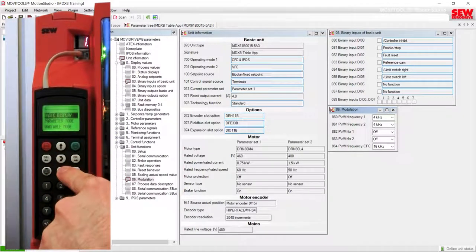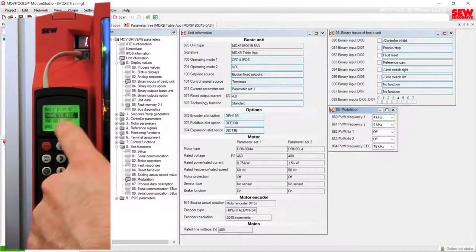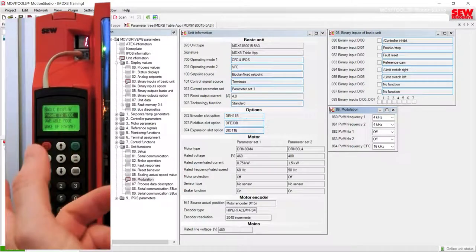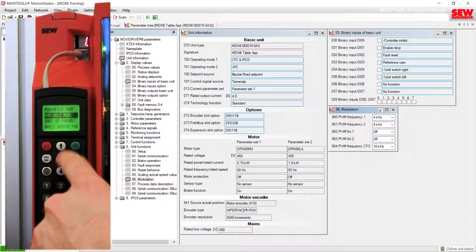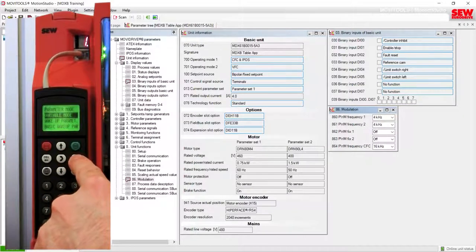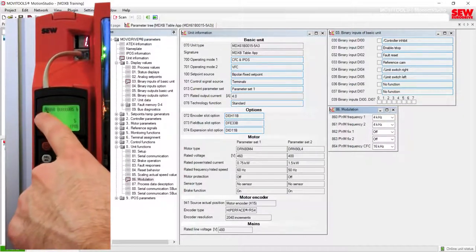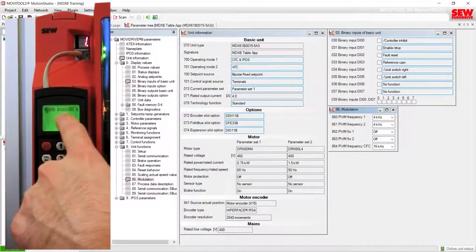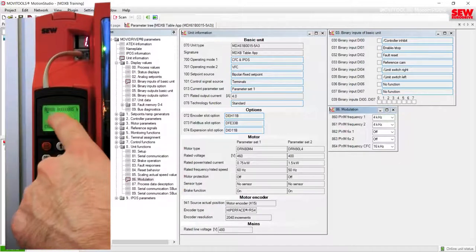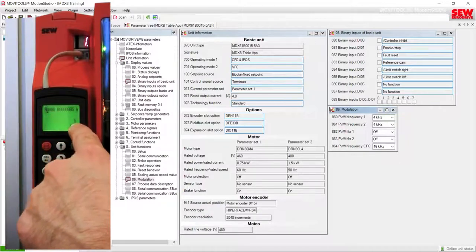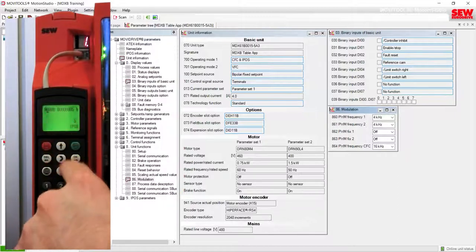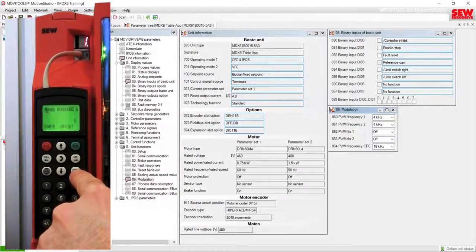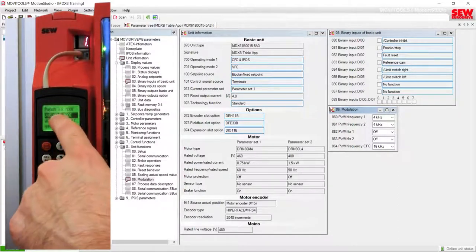Pressing the menu button again and then the down arrow brings us to the parameter mode, which allows you to view or edit parameters similar to the parameter tree in the software. The variable mode, if you press OK to enter it, is specifically for when you know the H variable number of an IPOS program that you have loaded — you can view or change that H variable if it's allowed. Pressing the menu key backs you out of that selection and returns you to the menu.